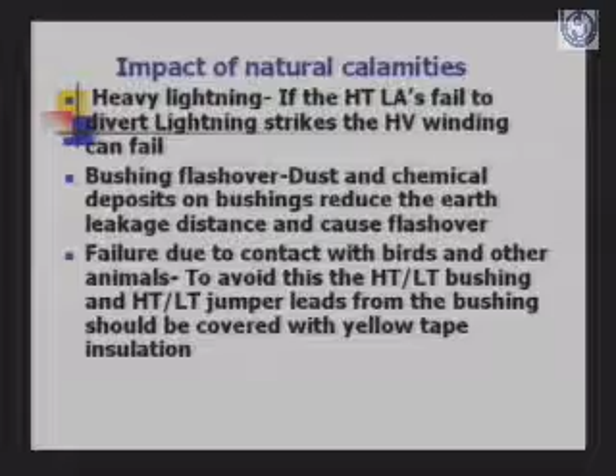Yes. So somebody was talking about the impact of natural calamities, that is heavy lightning. One of the natural calamities is heavy lightning. If the HT lightning arrester fails to divert lightning strikes, the HV winding can fail. Then there could be a bushing flashover due to dust and chemical deposits on bushings, reducing the earth leakage distance and causing flashover. That is also like a natural calamity, because if you have this in the vicinity of some factory or some power generating station, dust and chemical deposits on the bushings could reduce the earth leakage distance. Then failure due to contact with birds and other animals. To avoid this, the HT/LT bushing and the HT/LT jumper leads from the bushing should be covered with tape insulation. So these are some of the natural calamities which can strike a distribution transformer.